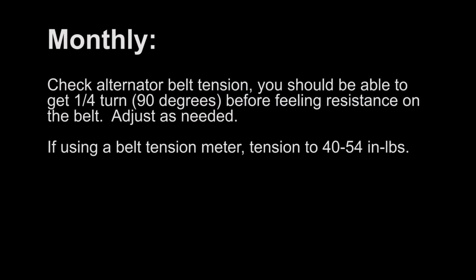Monthly: check the alternator belt tension. You should be able to get a quarter turn, or 90 degrees, before feeling resistance on the belt. Adjust as needed. If you're using a belt tension meter, tension to 40 to 54 inch-pounds.